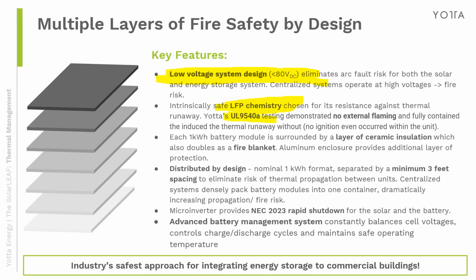We've gone through all of the testing, the UL 9540 and 9540A testing. During the testing we had no external flaming whatsoever. We had thermal runaway, but what was interesting is we couldn't get it to thermally run away throughout the entire battery pack because of our heat mitigation system. Any heat generated in the first battery pack was removed and put to the outside of the case, eliminating thermal runaway across the entire pack.